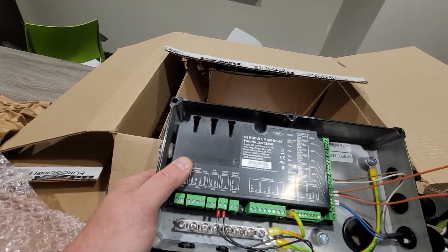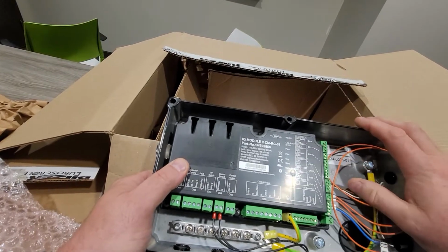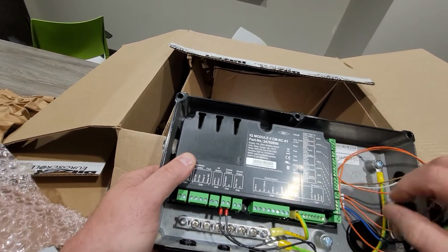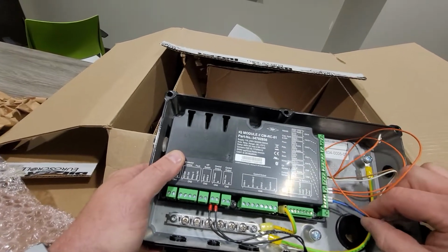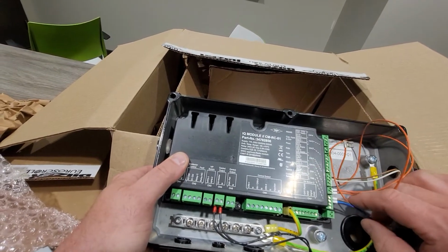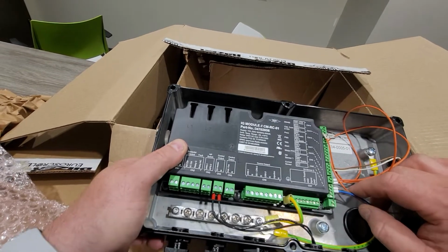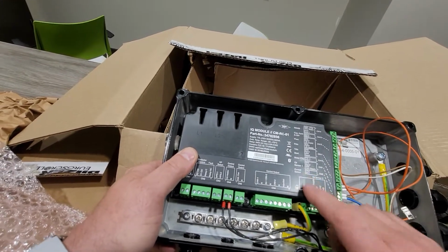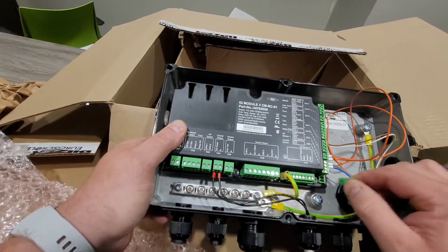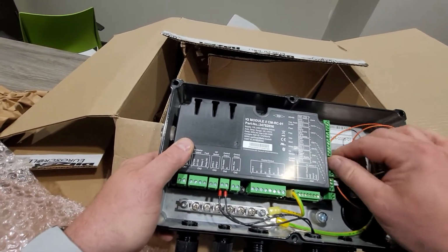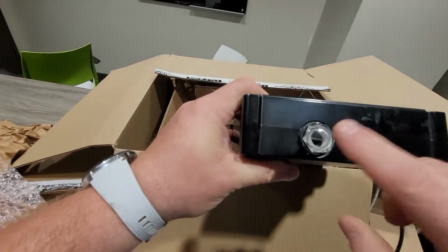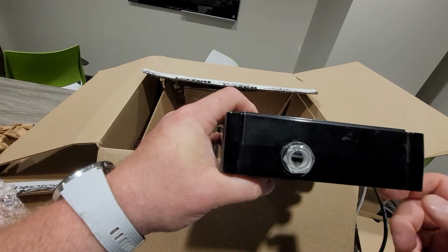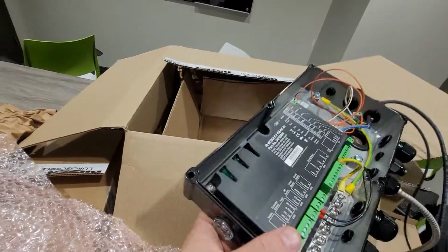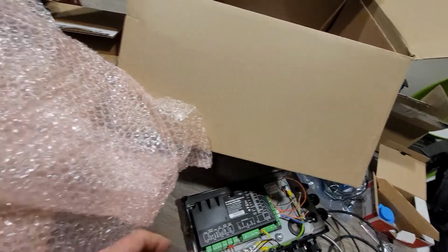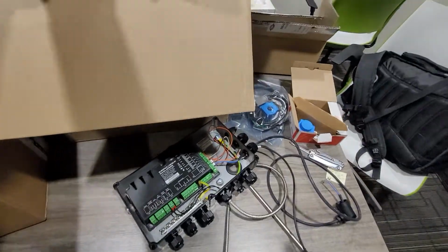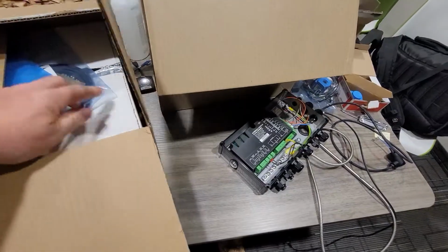That goes where that's embedded in the compressor, so you don't have that little box anymore. It's all on board with this. The oil pressure sensor, oil switch on this one, which is here. I do think it can take a pressure transducer as well, but I'd have to look at the manual for that. And current sensor. I do a digital output right here on all these little connectors that are on there. On the side here, you've got a little window where you'll see blinking LEDs for faults and Bluetooth, so you can connect your phone right to it. So this is a nice little package. Install that on a compressor, and you got some nice stuff going on.